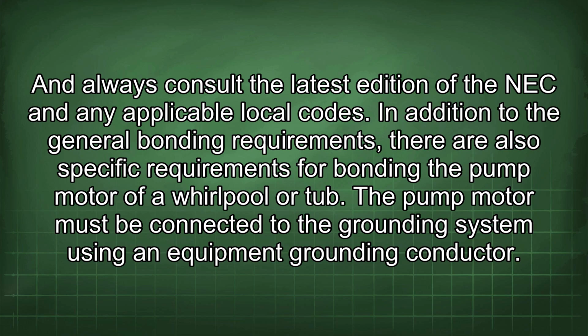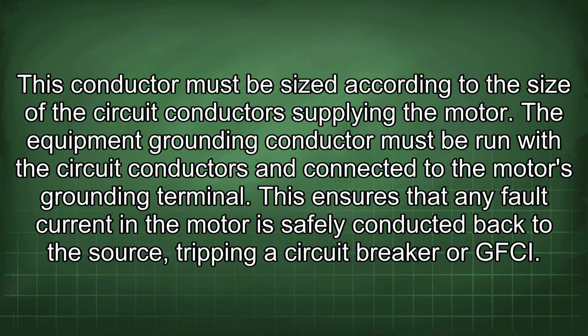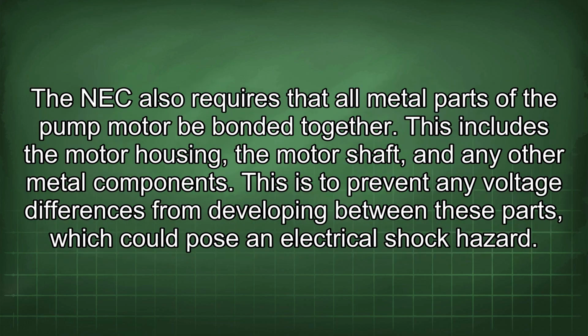In addition to the general bonding requirements, there are also specific requirements for bonding the pump motor of a whirlpool or tub. The pump motor must be connected to the grounding system using an equipment grounding conductor. This conductor must be sized according to the size of the circuit conductors supplying the motor. The equipment grounding conductor must be run with the circuit conductors and connected to the motor's grounding terminal. This ensures that any fault current in the motor is safely conducted back to the source, tripping a circuit breaker or GFCI. The NEC also requires that all metal parts of the pump motor be bonded together. This includes the motor housing, the motor shaft, and any other metal components. This is to prevent any voltage differences from developing between these parts, which could pose an electrical shock hazard.